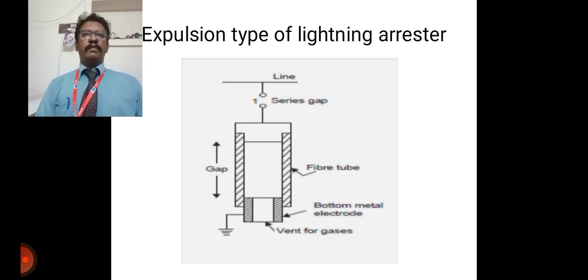An improvement of the rod gap is the expulsion type, which actually consists of a series gap, as I said earlier, external to the tube, which is good enough to withstand normal system voltage. Thereby, there is no possibility of corona or a leakage current across that particular tube. Next, you can see here a tube which has a fiber lining. You can see inside you have a fiber lining on the inner side, which is made of highly gas-evolving materials.